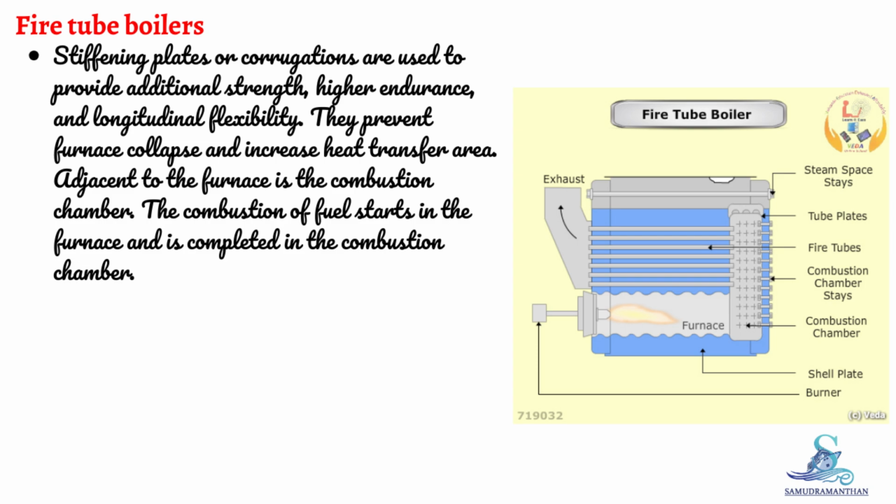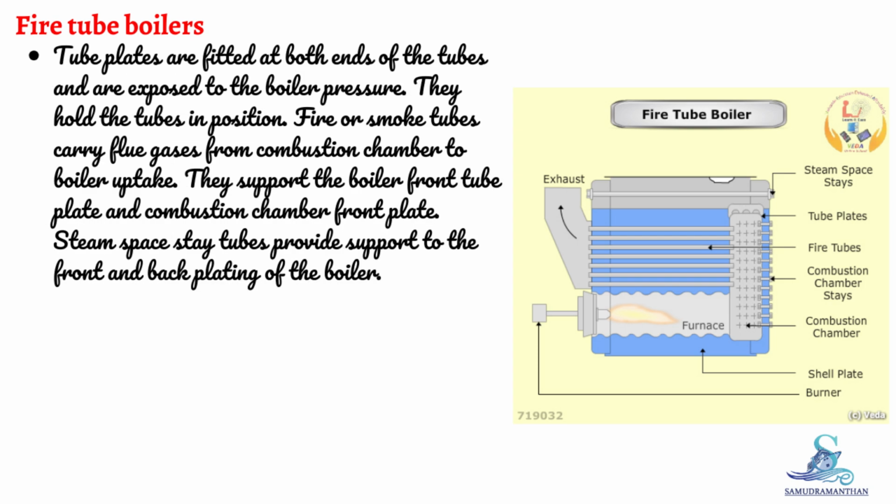Adjacent to the furnace is the combustion chamber. The combustion of fuel starts in the furnace and is completed in the combustion chamber. Tube plates are fitted at both ends of the tubes and are exposed to the boiler pressure. They hold the tubes in position.